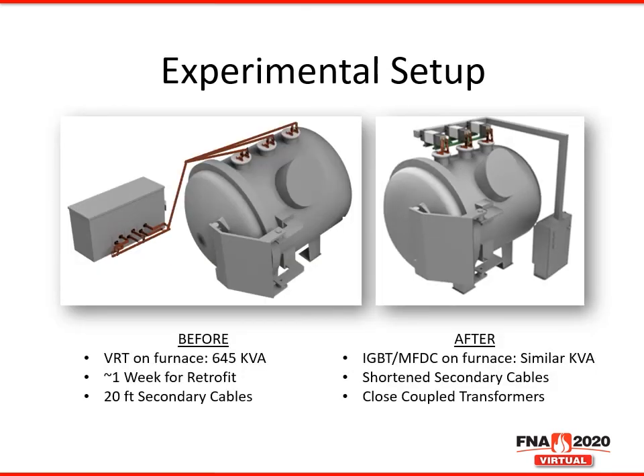Here, you can see the details to the vacuum furnace retrofit. On the left, we have the VRT and vacuum furnace as it was originally built. The furnace VRT was rated at 645 kVA. There were 20-foot water-cooled cables that went from the VRT to the power feed-throughs on top of the furnace. It took approximately 1 week to remove the VRT and place the IGBT MFDC system, which you can see here on the right.